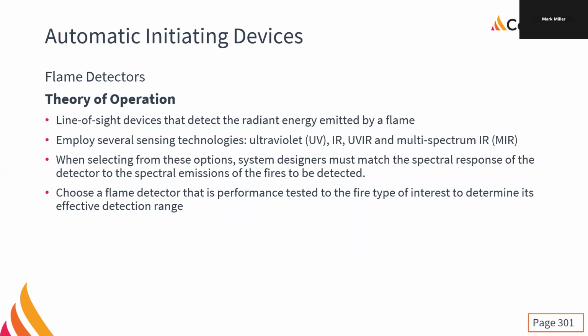So we've got two different types. They are line of sight devices. Of course, they are flame detectors. They have to be able to see the flame. They detect the radiant energy that is emitted by a flame. And we've got two types. We've got ultraviolet and infrared. So both ends of the visible spectrum. And then we've got the multi-spectrum ones that will do both, and it can kind of cover the entire range.